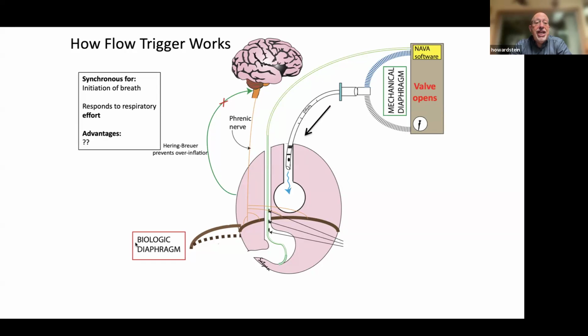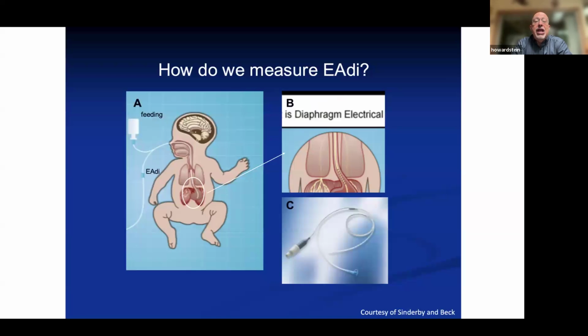This is synchronous for initiation of the breath only, and it responds to the patient's effort. The patient actually has to move air in order for the flow trigger to be useful. We measure the EDI, or the electrical activity of the diaphragm, with a specialized catheter. It looks like a regular nasogastric tube, but it also has an electrical cable built into it. There are little electrodes on the end that we position right at the level of the crural diaphragm. That can then detect when the electrical activity of the diaphragm begins, how much electrical activity there is, and when it ends. Here you can see that the tip is in the stomach. It can be used as a regular feeding tube, and the electrodes are positioned at the crural diaphragm.